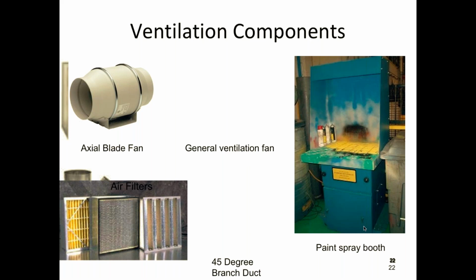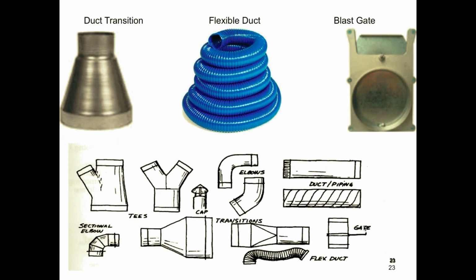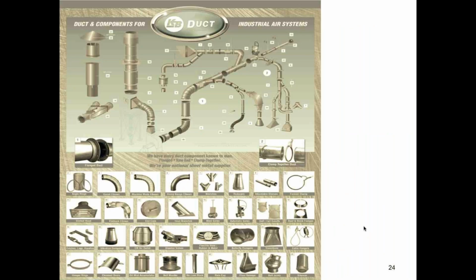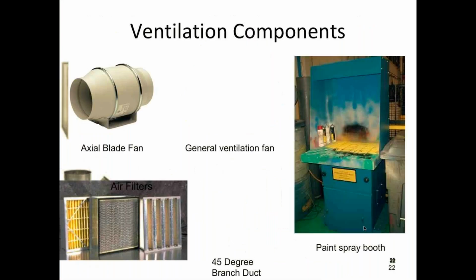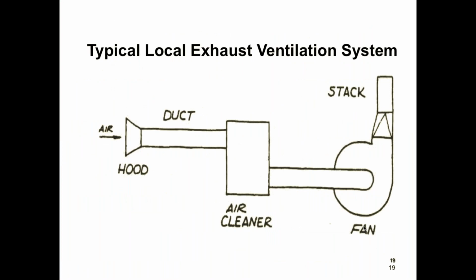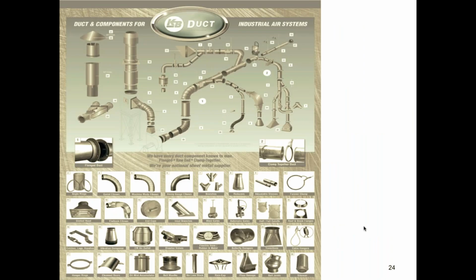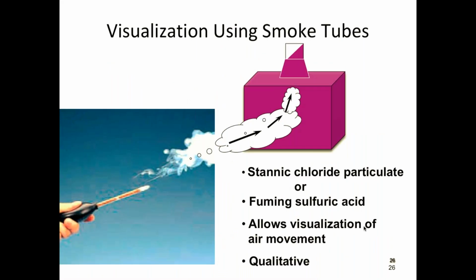So, ventilation system components. This is an axial fan blade. You have many other different kinds of systems. This is a paint spray booth. It's just a booth that you're pulling air through. They're just using aerosol cans there. You can have systems on ductwork where you have elbows, where you have transitions, and so on and so forth. Once you start to design or look at these systems, they can get pretty complicated in terms of the transmission equipment. But the basics are always going to be this idea of a hood, transmission system, ductwork, an air cleaner, and a fan. Okay, you're always going to have a certain amount of that going on.